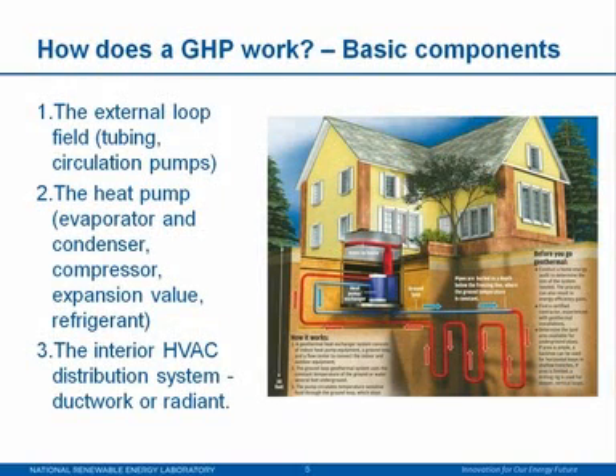And so how does the ground source heat pump system work? This is a basic diagram of the components of a ground source heat pump system. You have three basic components. You have the external loop field. In this picture, it's shown in the bottom right-hand corner, where you've got the blue and red piping running underneath the ground. It's basically piping or tubing buried underground that has heat transfer fluid flowing through it. That's the external loop field. The second main component is the heat pump unit itself, which includes an evaporator, condenser, compressor, expansion valve, and refrigerant, all in one contained unit that would be located inside the structure, probably in the basement, much like any other furnace.